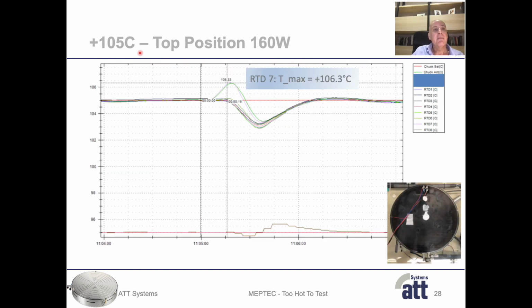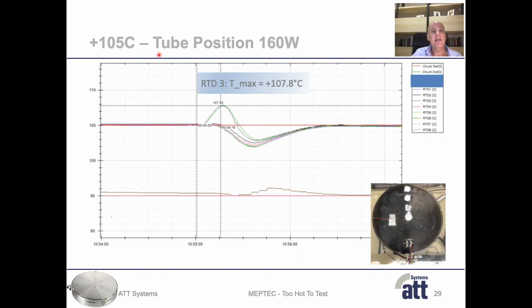Then we changed the temperature to plus 105 degrees C and tested the system capability with an applied power of 160 watt. First test was done at the top position. The test time was 15 seconds, and RTD7 became the control sensor, and the system was able to keep the temperature below the specified 108 degrees C. The second test has been done at the tube position. RTD3 became the control sensor. The maximum temperature was 107.8 degrees C and also within the specified limit of 108 degrees.